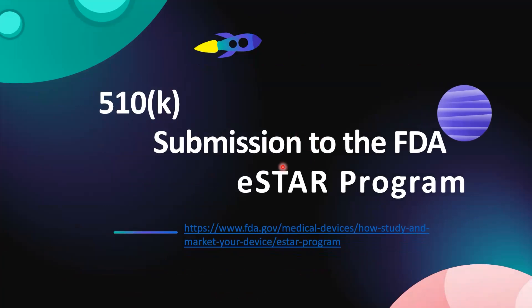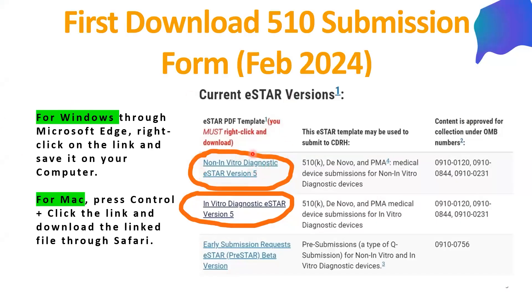The 510-K submission is through the eStar program, described by the FDA as an interactive PDF form that guides applicants through the process of preparing a comprehensive medical device submission. You can download the latest version of the eStar PDF document from the website given in the comments section. For Windows through Microsoft Edge, right-click on the link and save it on your computer. For Mac, press Control and click the link, then download the file through Safari. In this presentation, we are describing version 5 of the eStar, and there are two types: non-in-vitro diagnostic eStar and in-vitro diagnostic eStar.